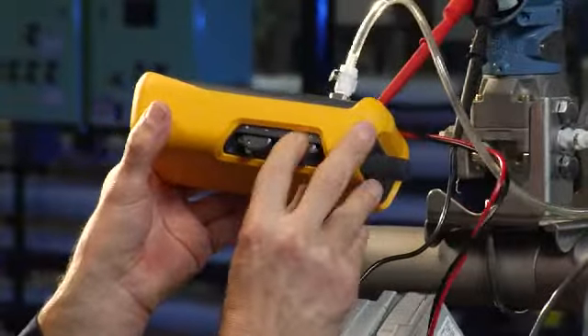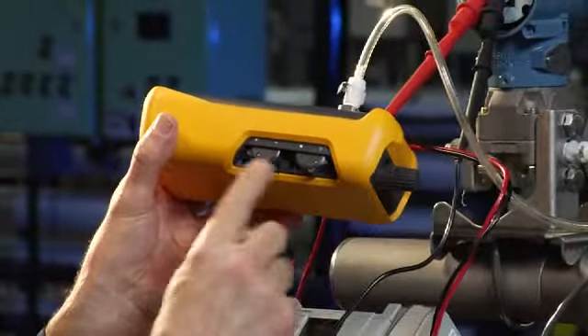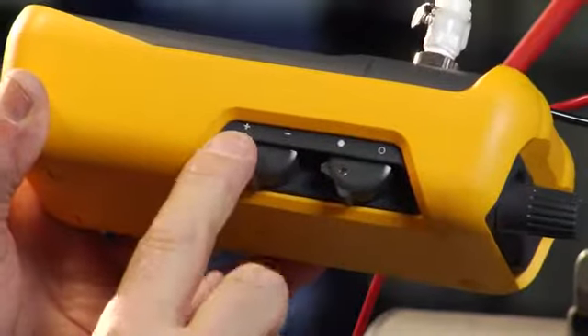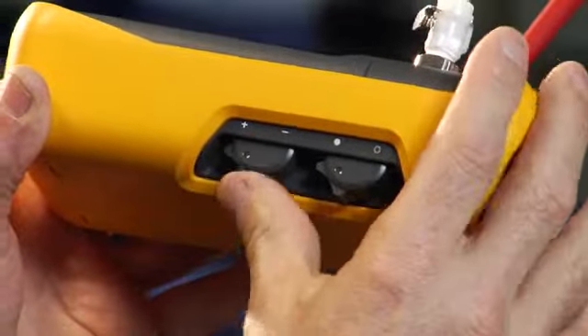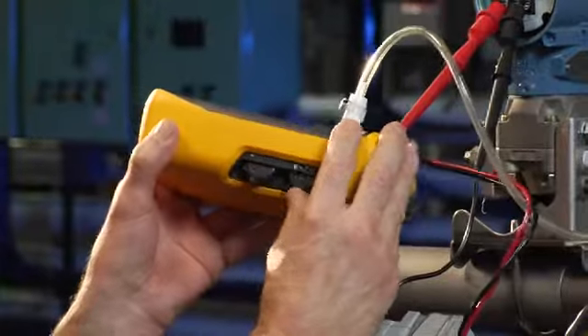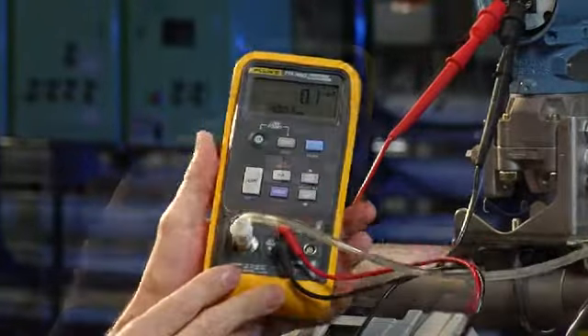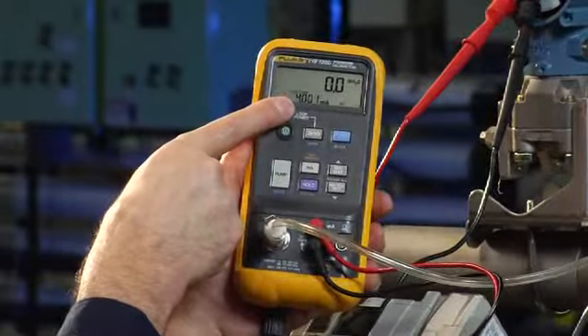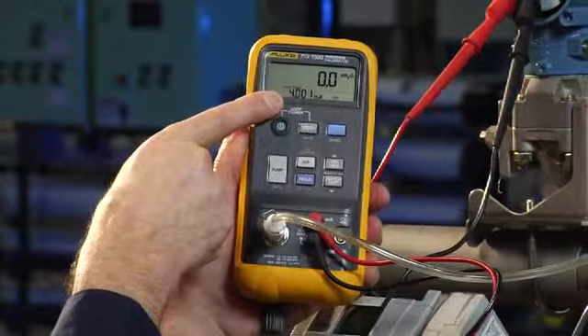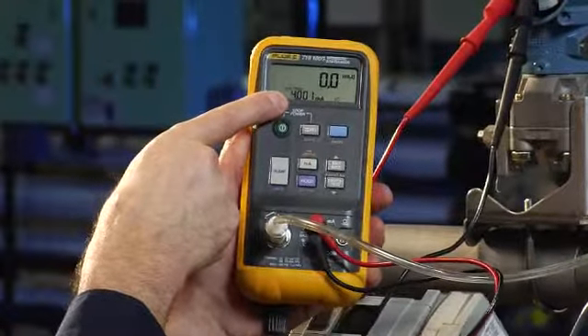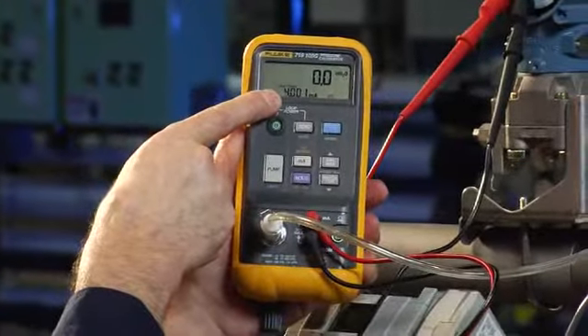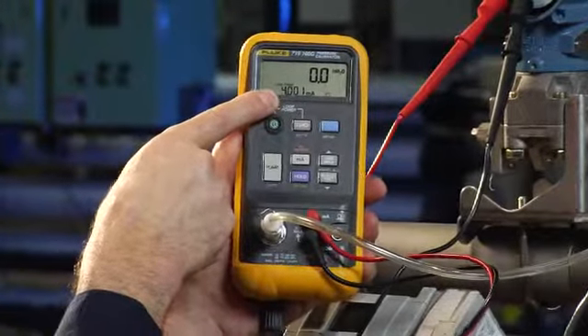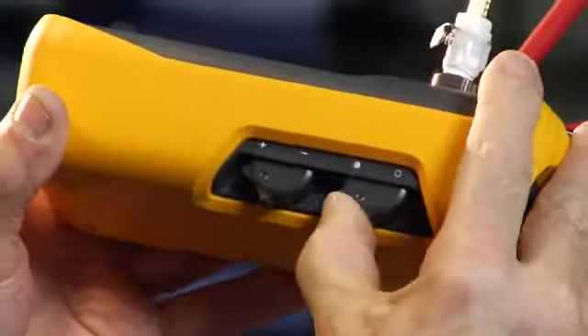Open the vent valve. The vent valve can be opened or closed. Open for measuring the 0 inches of water point. This pressure vacuum switch allows you to pump either positive pressure or negative pressure. For this example, we're going to measure positive pressure. First, we apply 0 inches of water. Measure 4 milliamps. Any deviation from 4 milliamps is calibration error. Next, close the vent valve.